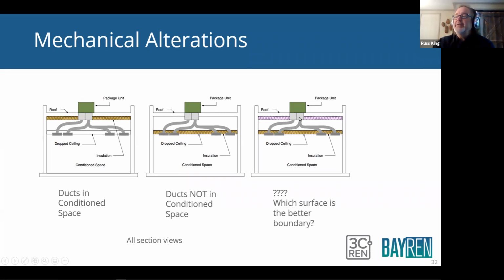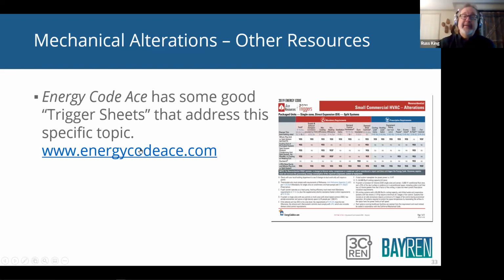If it's at both locations, you just have to decide which of these boundaries, the insulated roof or the insulated T-bar ceiling, is a better thermal boundary. And in most cases, it's going to be the roof because, as I said, T-bar ceilings make horrible air barriers. But if this is not a T-bar ceiling, if this is a sheetrock ceiling with insulation on it, that's probably a pretty good thermal boundary. Then you have to look and say, all right, is that attic ventilated or not? So it's a judgment call. But what you're looking for is: is the location of the ducts more like conditioned space or is it more like outside? Right. All right. So that was a lot of information I just threw at you.